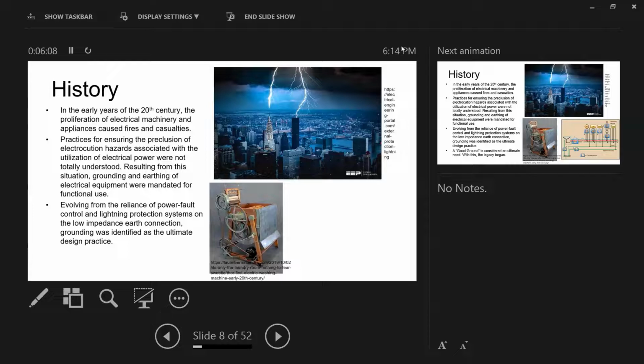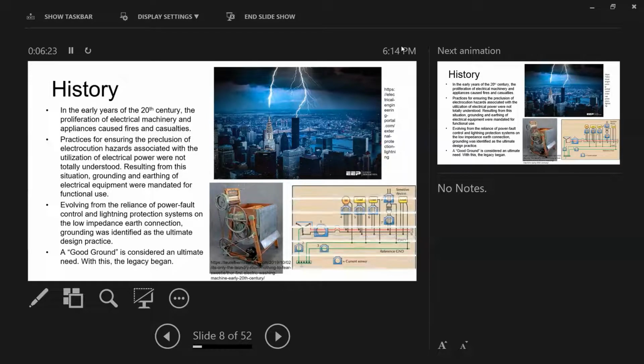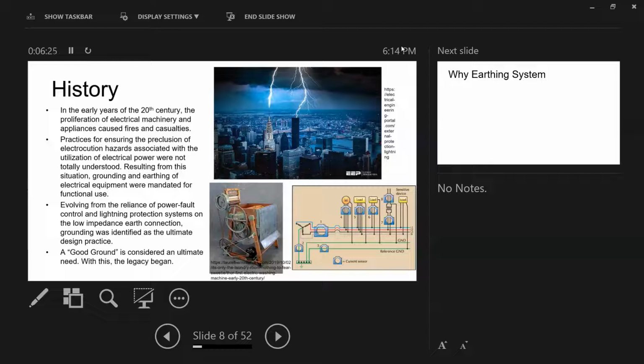So to avoid all these issues, after a thorough investigation, they found that to have a safe and reliable electric machine, a safe and reliable system from a lightning perspective, and a safe and reliable power network, you must have an earthing system. Earthing system, it's our ground. The ground is not only an area where we physically build on it or stand on it, or put our transmission line, substation or power station. No, it's actually an element.